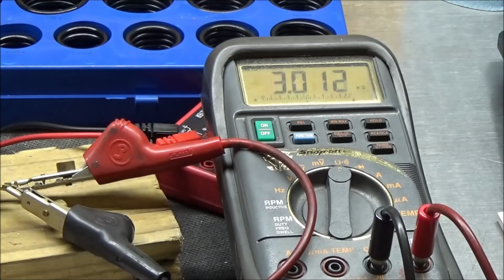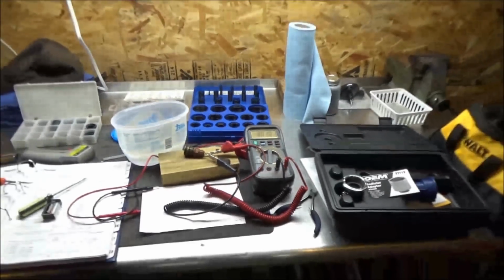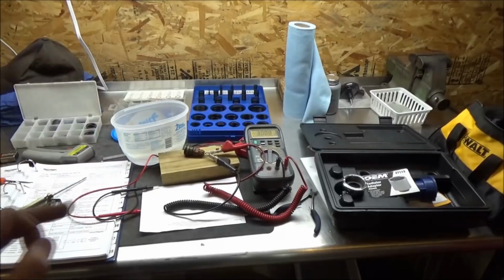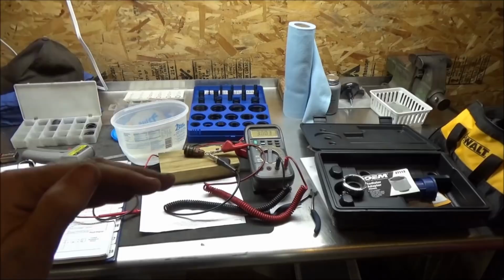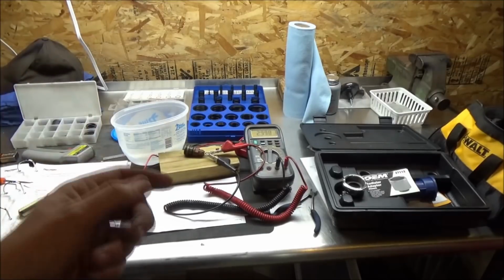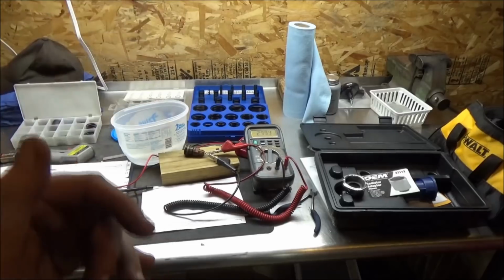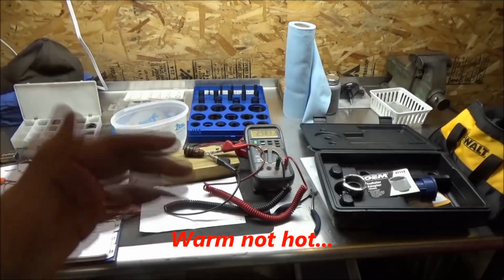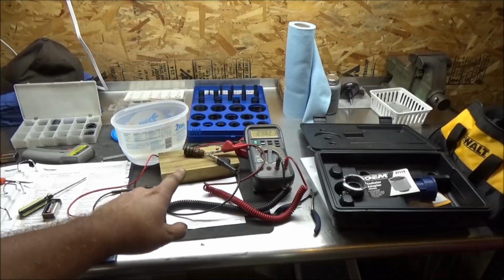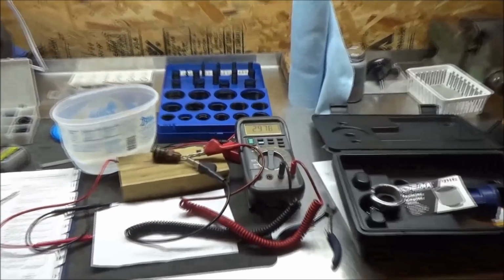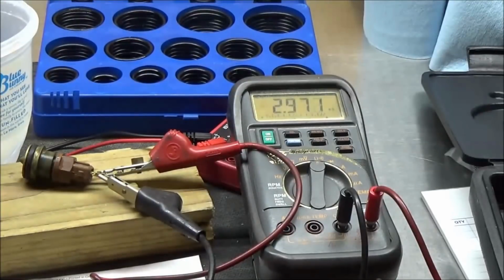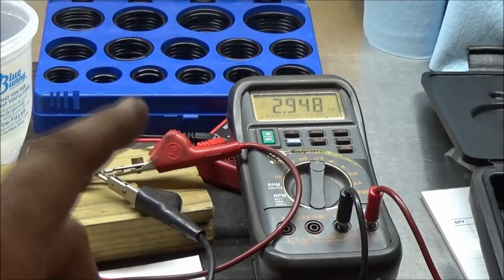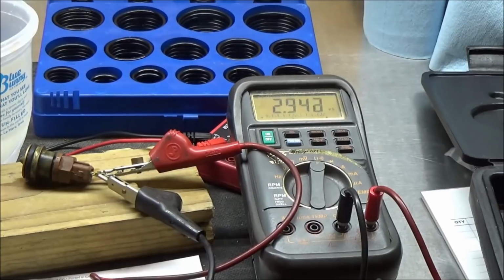Here's the important part, let's do a little summary. The key thing is that I was able to see the sensor change through the temperatures - that's really crucial. Ideally I'd even take a heat gun and go hot to prove it goes that direction too, but we started hot, so we know it has that ability. Even just sitting here in this hotter shop now out of the water, you can see the numbers keep dropping as it takes on the ambient room temperature, which changes the resistance. So that sensor is functioning as it needs to, and I can eliminate it from my checklist of potential causes for this cooling system problem.